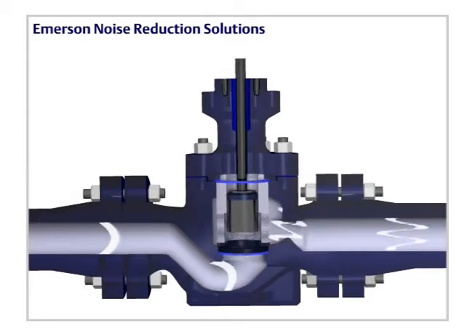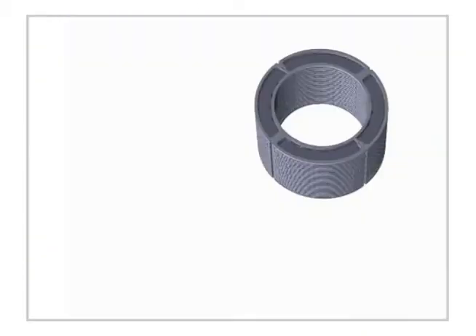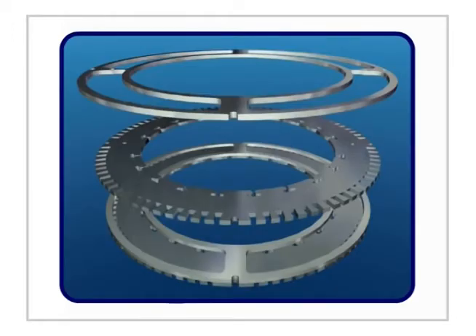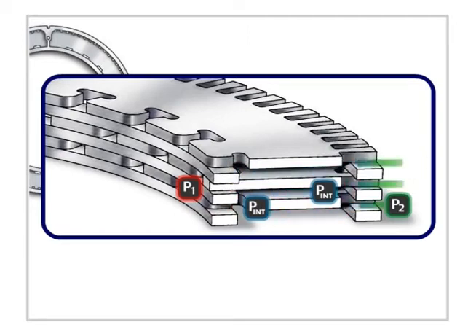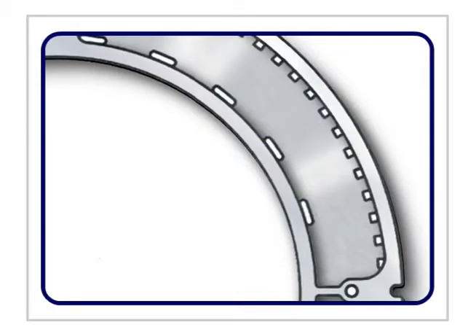Source treatments include the Fisher WhisperFlow model. Its unique passage shape reduces turbulence to minimize shock-associated noise, and places turbulent shear layers away from solid boundaries to reduce dipole noise. Multi-stage pressure reduction is employed: the first stage pressure drop ratio is greater than that of the second stage, reducing acoustic conversion efficiency for low pressure ratios. The design controls jet size formation, interaction, and accommodates the fluid expansion.